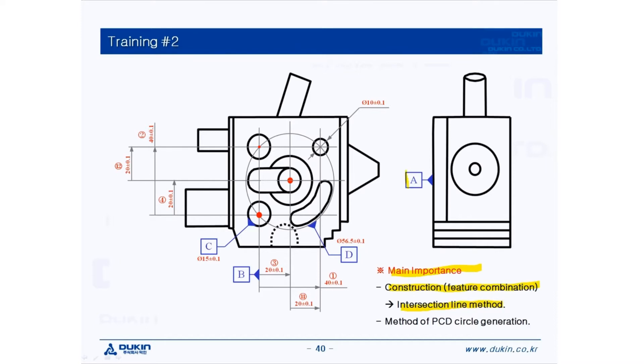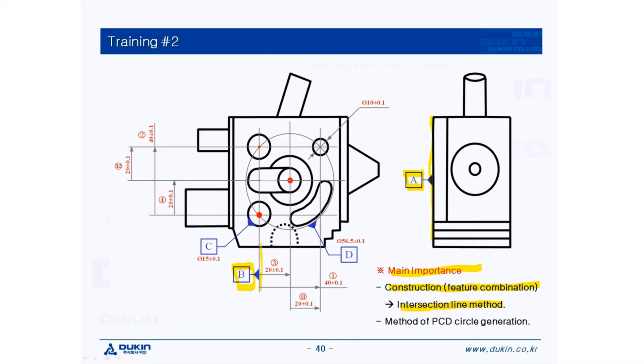Let's take a look at datum A first. Same as training number one, top surface of the sample for leveling. And then let's take a look at datum B. Datum B is a line that crosses the two circles' center. So measure two circles first, and then we're going to create a line that crosses the two circles' center.